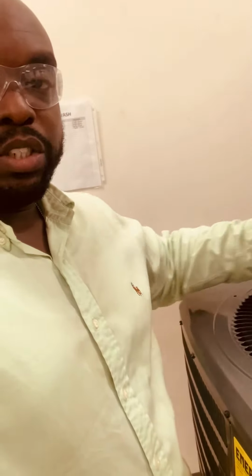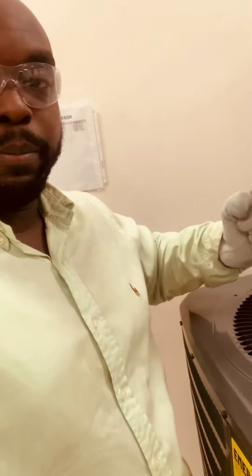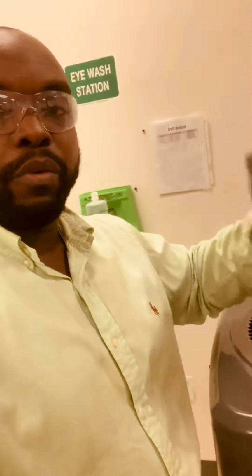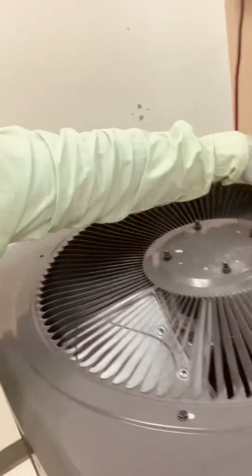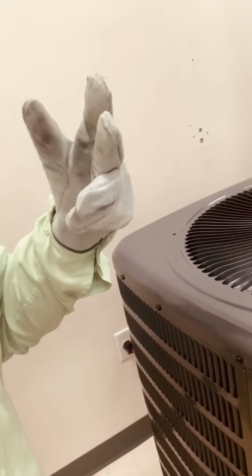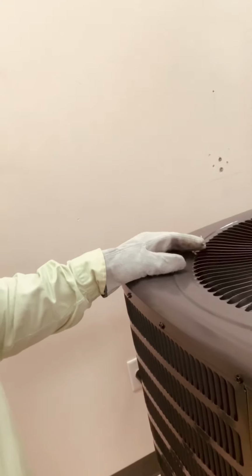Now, it's going to take in that suction gas, low pressure, low temperature. It's a pressure increaser. So with that pressure increaser, it's going to bring it to a high temperature, high pressure, superheated vapor. Now, also keep in mind, the compressor is actually adding heat as well, heat of compression. The condenser coil, which is this whole thing here, is going to go through 3 phases. The first phase is going to be de-superheat.